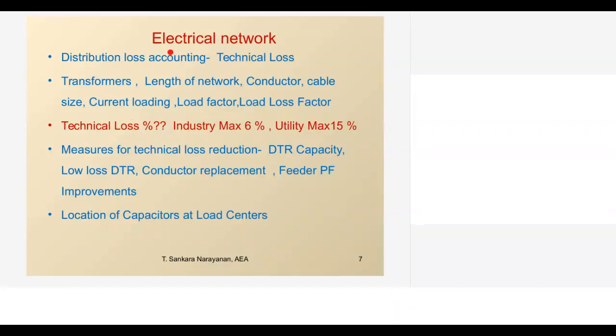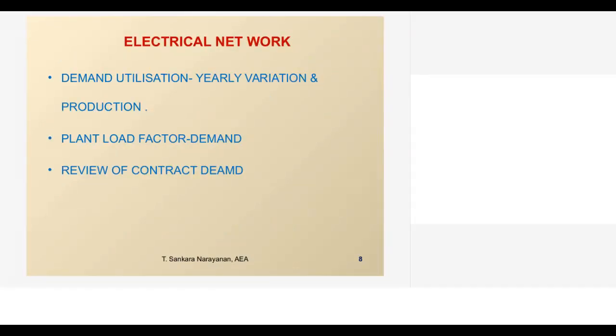At least in both these cases, especially industry, we should be able to account for all the transformer losses, then major feeder losses. So if we want to reduce distribution loss within a plant, then we have to go for installing capacitors nearer to the load centers. So again, there are certain guidelines on how to put the capacitors. We will also see that.